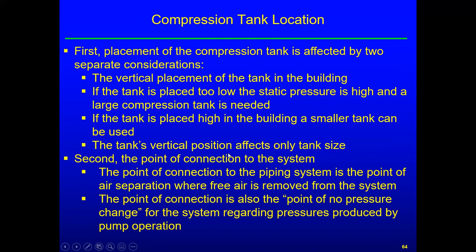Second, point of connection to the system. And these are pretty important. The point of connection to the piping system is the point of air separation where free air is removed from the system. So we need to note that for sure. And the point of connection is also the point of no pressure change for the system regarding pressures produced by pump operation. So all three of those: vertical location in terms of static pressure, air separation, and point of no pressure change. All important.